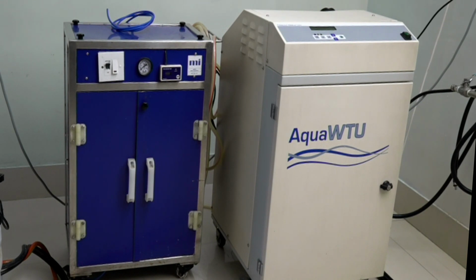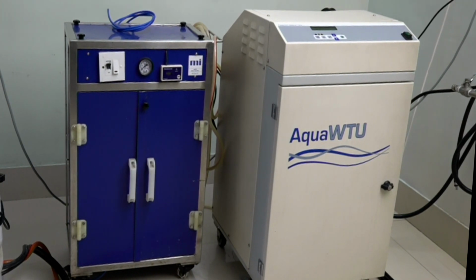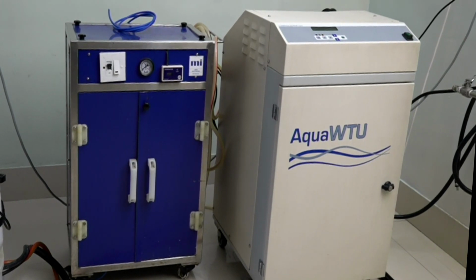We need ultra pure water, traditionally done with the aid of double pass reverse osmosis. However, in units in our country which perform both hemodialysis and online hemodiafiltration, it may become wasteful to have all water processed by a double pass RO. We circumvent this problem by using highly purified water. It's a single pass reverse osmosis system, and then introducing a portable reverse osmosis unit between our normal water line and the dialysis machine. If you can afford it, Fresenius produces a portable RO machine called the Aqua WTU, which produces about 100 liters per hour of water.